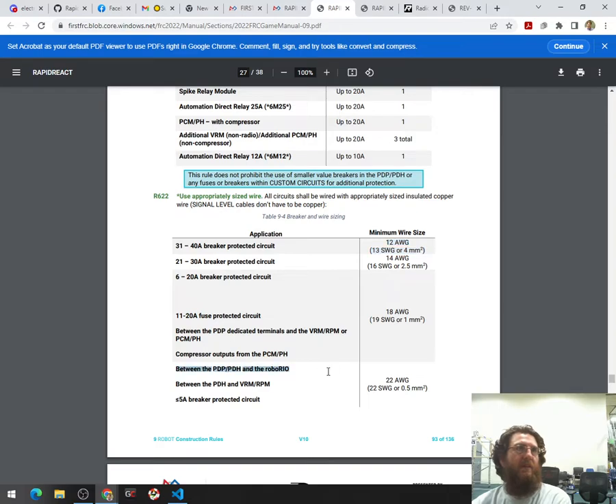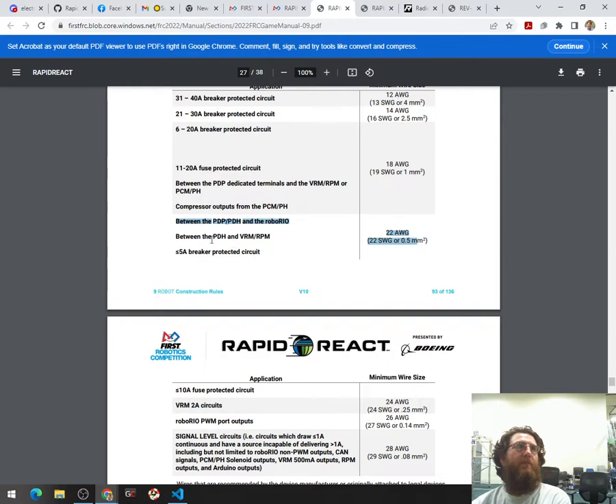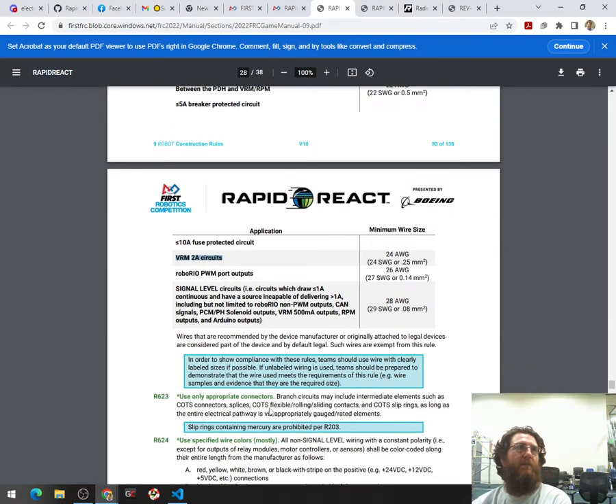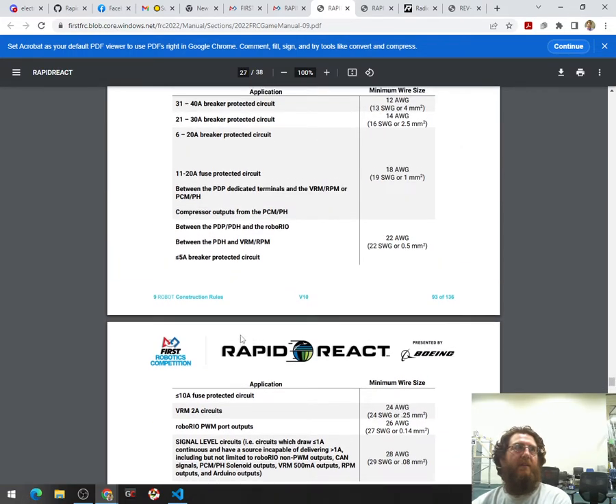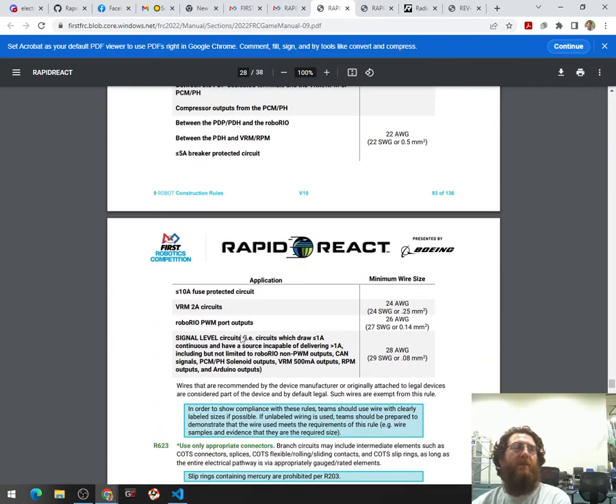Also 22 gauge for certain things less than 5 amps, and other circuits like signal level circuits, for example 24 or 26 gauge, can be used. Things like limit switches have to be at least 28 gauge. Anyway, that's a handy chart to know which wires need to be which sizes.